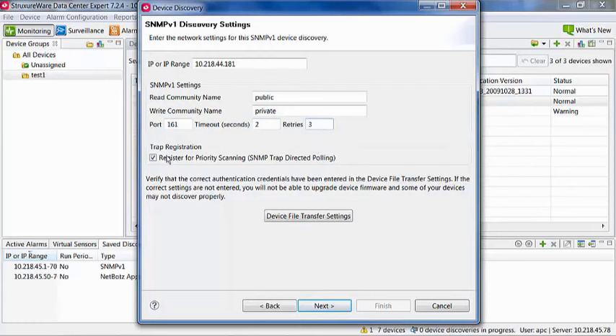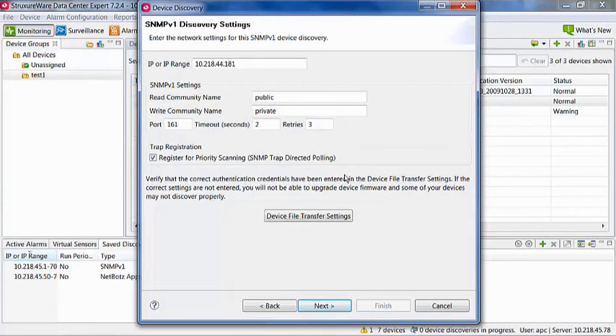Trap registration for priority scanning is for APC devices only. Using this functionality, we will set a hidden trap receiver on the device so the normal trap receiver fields are still available for customer use. When we do receive a trap using this functionality, we re-poll the APC device to verify there are actual issues.